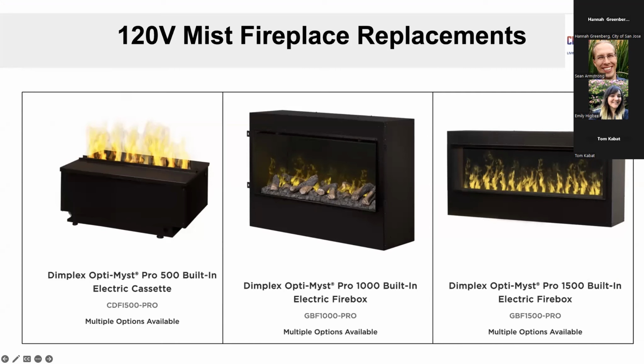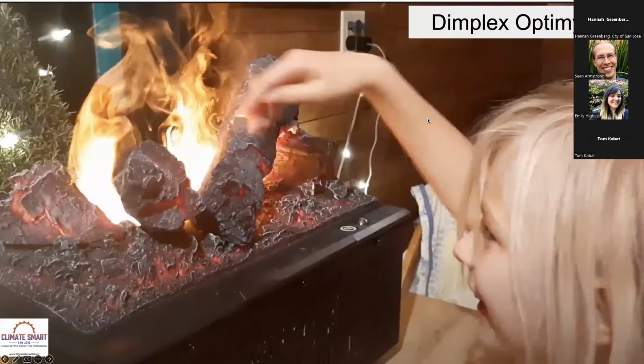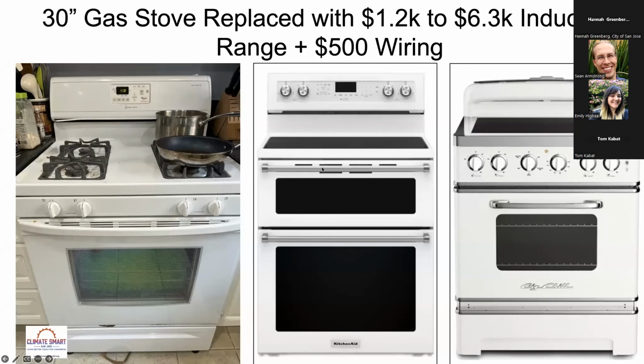Randy, you asked, aren't you going to need a 40 amp circuit for that Whirlpool induction range? Yes, but interestingly, that 40 amps, when you put it onto a house panel, is derated by 60%, meaning that instead of looking like 40 amps on your panel, it looks like 16 amps. That's one way of doing it under code. Another way is if you've studied your panel and found you peak at 25 amps, you add a little buffer so now it's 30 amps, and you can add something at full rated, so 40 amps for a stove. 30 plus 40 is 70, and you still haven't gone over the 100 amp threshold in either of the two code-approved ways to add this 40 amps. Regardless, the answer is that your 100 amp panel is big enough for a 40 amp stove.